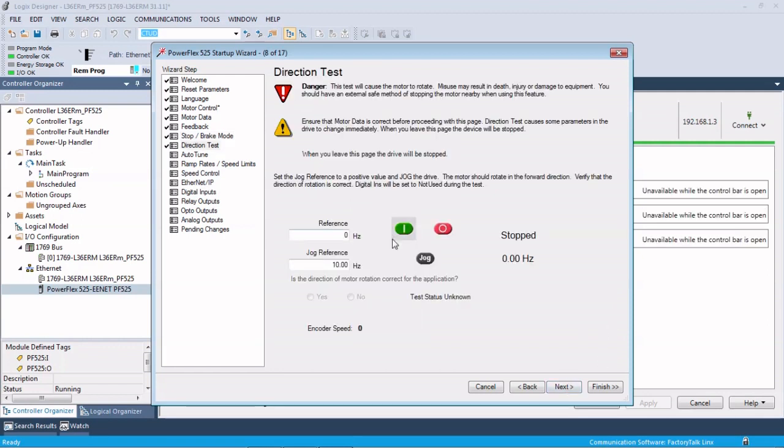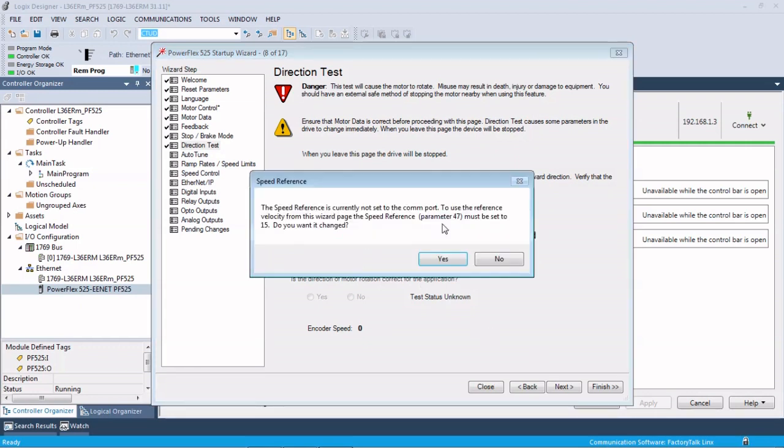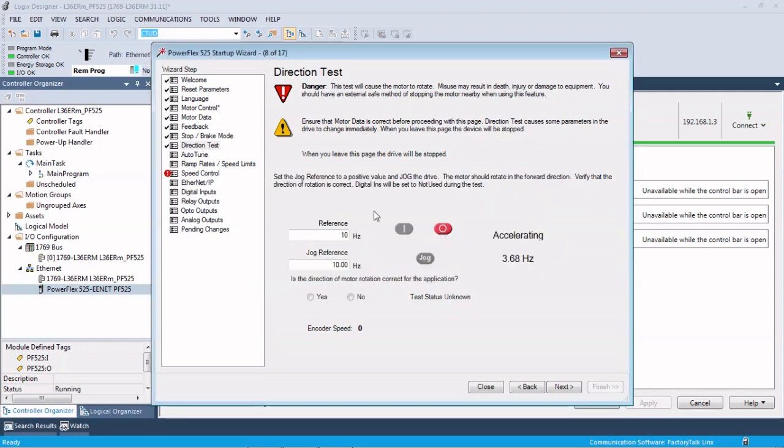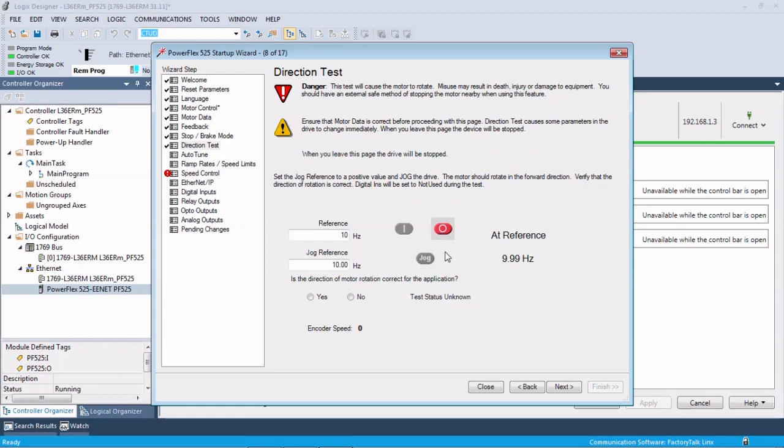So direction test. Here we would put in a reference, say 10 hertz, and we hit the start. And this is already going to yell at us for something. Right now our motor is running. We would look at the motor to make sure we're running in the right direction. We'd stop it, and then is the motor running in the correct application? We hit yes and move next.